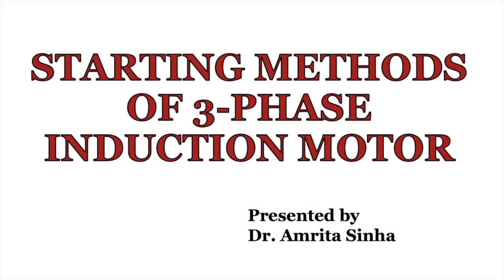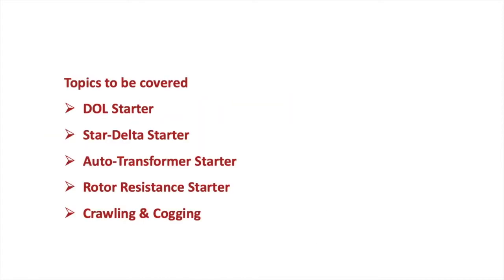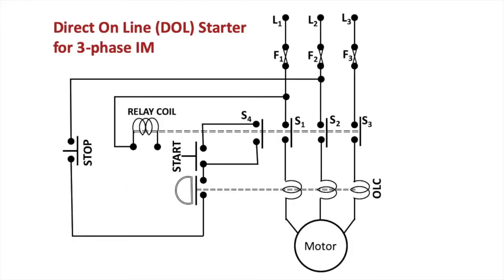Discussing the starting methods of three-phase induction motor. The topics to be covered today are the DOL starter, star-delta starter, auto transformer starter, rotor resistance starter, and two features sometimes seen in the induction motor where it fails to run, known as crawling and cogging. So the first is the DOL starter for three-phase induction motor.